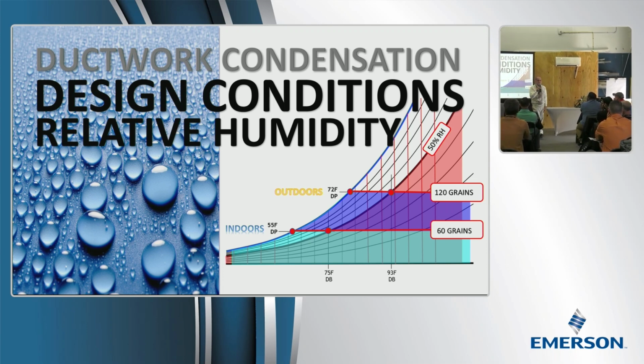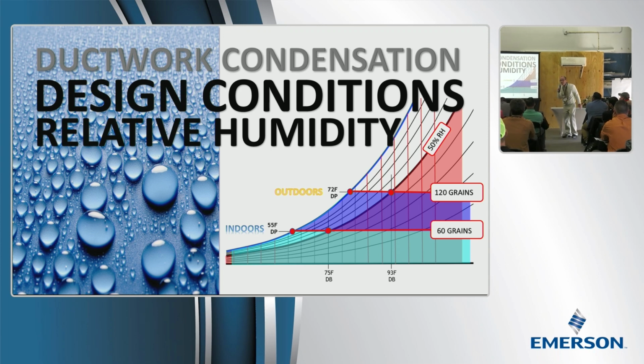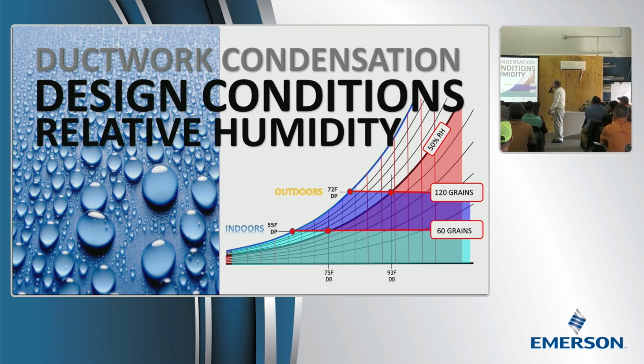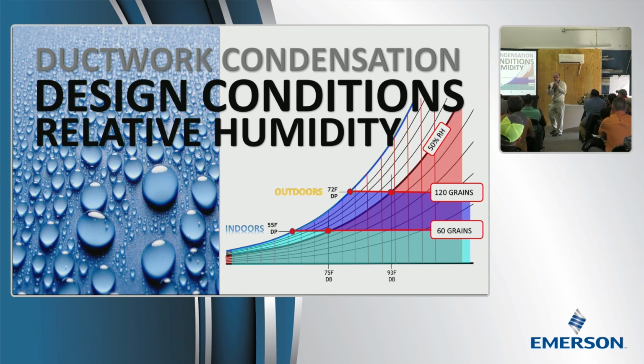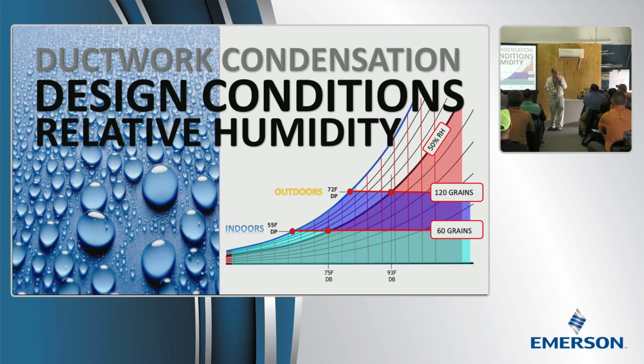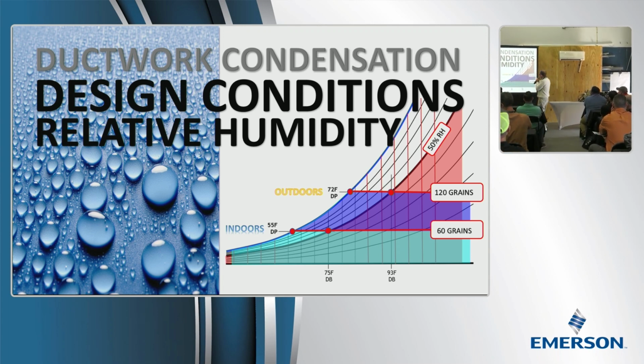They're both at 50%. It's just that 95-degree air can hold a lot more moisture, and so 50% would be 120 grains. I love the math for climate zone 1. Look at the grains. It's exactly double. It's exactly twice as much moisture per pound of air. So how do we use this?